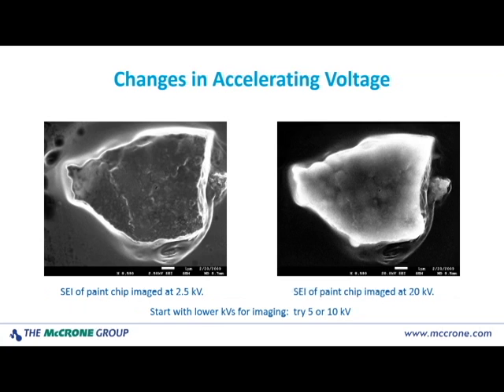Here's a paint chip showing the penetration effect of the beam. On the left at 2.5 kV, we get very nice structural detail of the surface and can see small features on that surface. But if we increase the accelerating voltage to 20 kV, the quality of our image has degraded. At higher kV, we have a smaller diameter beam and it should give us better resolution — but resolution is not image quality. What is happening is we're impinging too deeply, getting too many signals from too many planes, and we lose the structural detail of the surface. So if you're looking for imaging, you're going to back off and go to that lower kV. If you're going to do elemental analysis, you're going to maybe need this higher kV. So the optimum conditions for imaging are not the same as our optimum conditions for doing our elemental work.